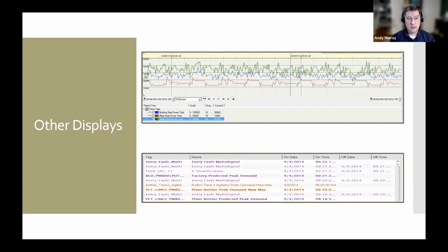Alarming is also a main function of a SCADA system. It's either built into the SCADA system, where you have screens like the bottom half of this slide listing the element, a descriptor of what happened, and the on and off times when the alarm got acknowledged. Both these pieces of data are oftentimes put into a database in the back end so it's stored and logged, and you can use your system to look back. Obviously, with trending you need to store that data to look at the history, but the same goes for alarming.